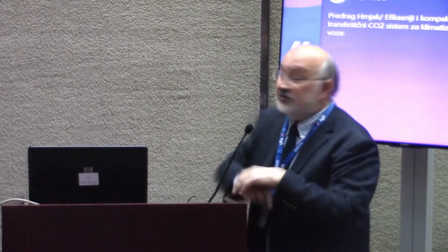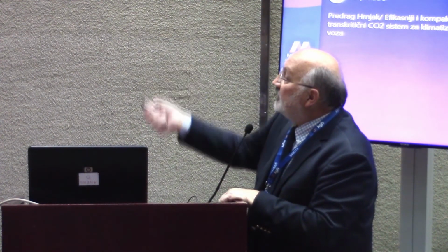Here on the top left is our baseline, the way it looked when it came to us. The system was supposed to make 44 kilowatts at rating condition, with ambient at 35 degrees C, and indoor condition at a relatively high temperature, around 27 to 29 degrees C, very high. I insisted on getting the baseline system they use today, which uses 407C. The reason they use 407C is that it didn't change too much from R22, making it the simplest replacement. Here I'm showing some other designs.